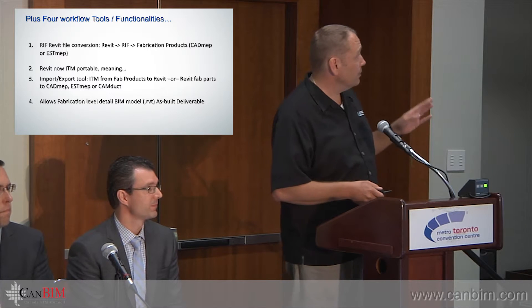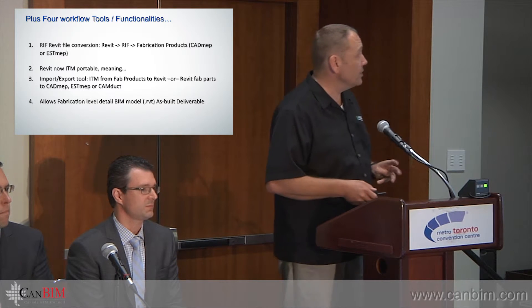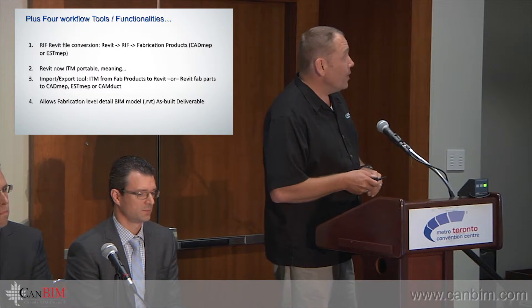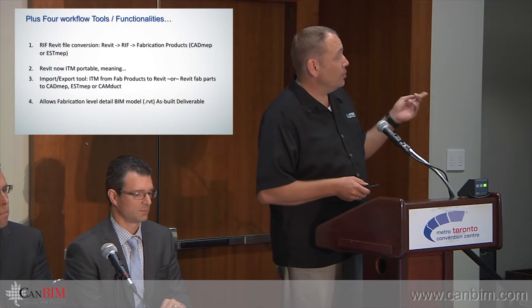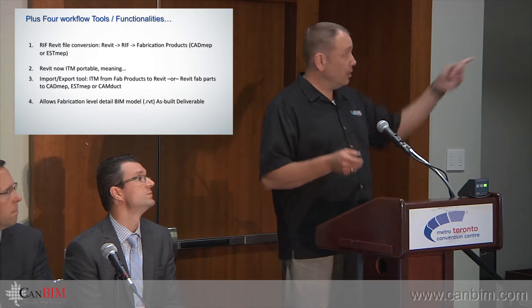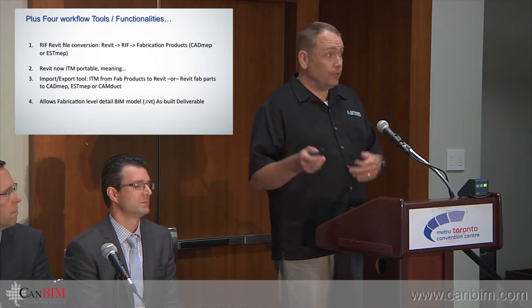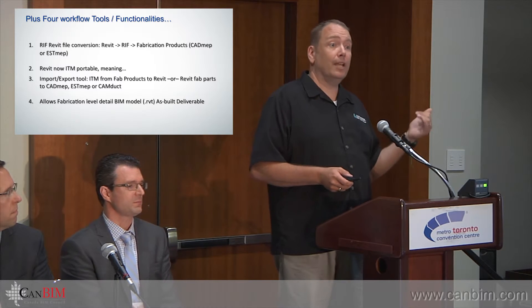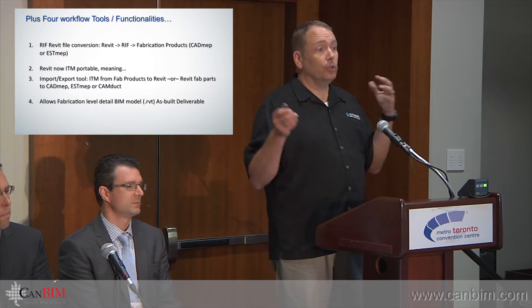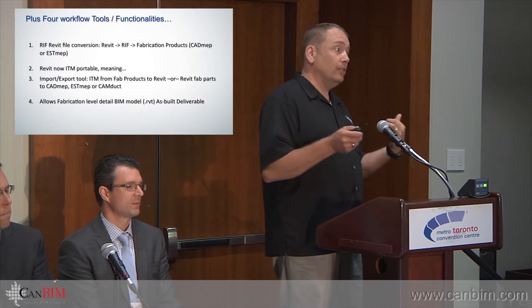The new workflow tools and functionalities include RIF file conversion. If you want to go from Revit to the fabrication products, you export the Revit file as a RIF file, then open up the fabrication products and bring those in — you can bring it into CADMEP or ESTmep. Revit is now ITM-portable, meaning that you can import and export ITM content from CADMEP back into Revit.